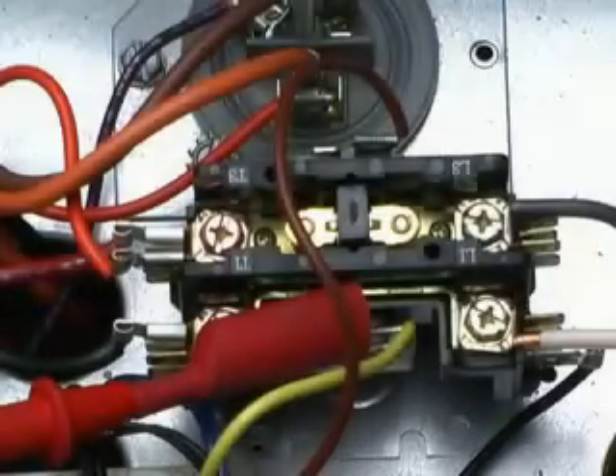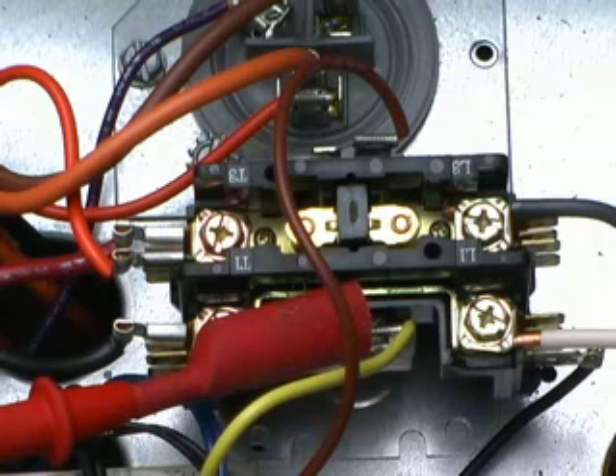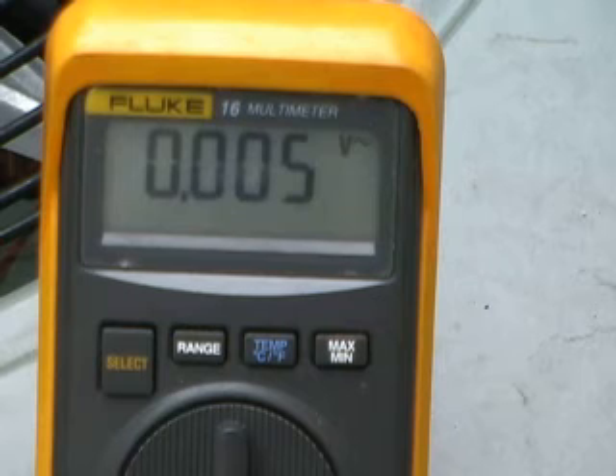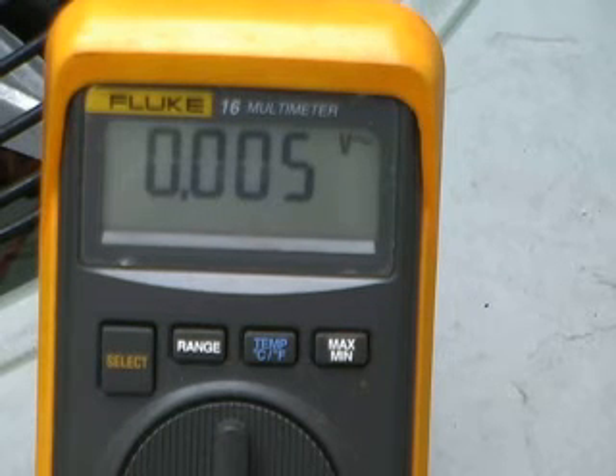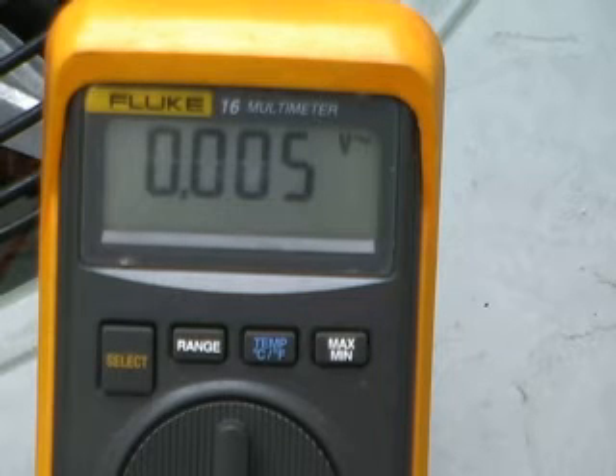So if we came on this unit and saw that the contactor wasn't pulled in, we could go to the hot side of the contactor coil with our probe and see if we were reading 24 there. Of course, just about be sure you're not. And as the meter says, we're not getting any voltage there. So then we have to back up to the next junction in that circuit, which is going to be the Y out terminal on that defrost board.